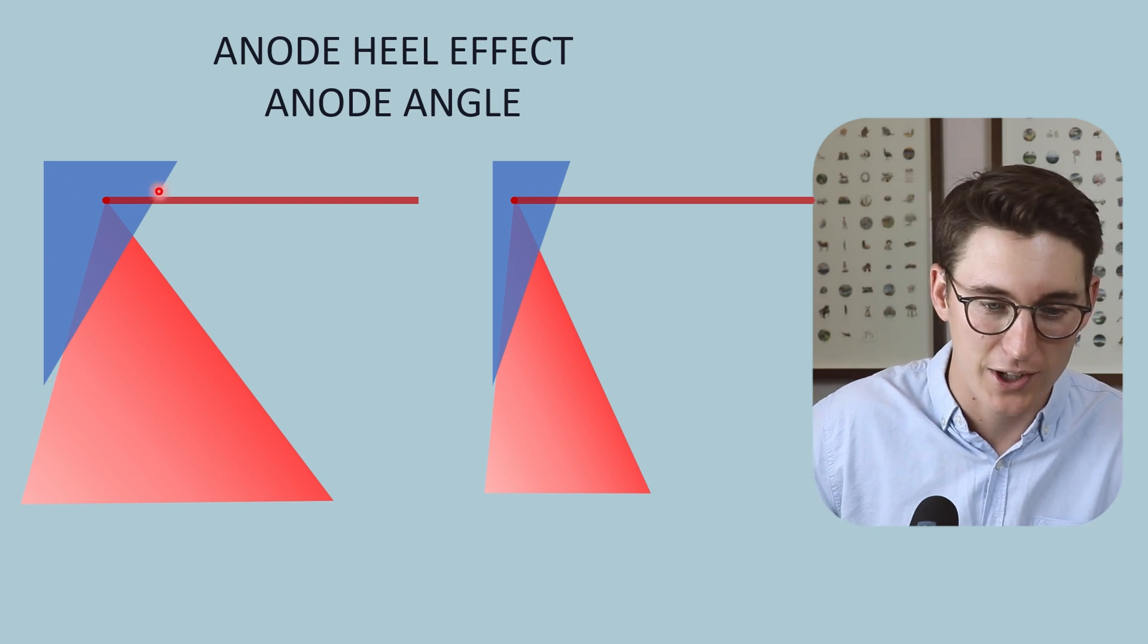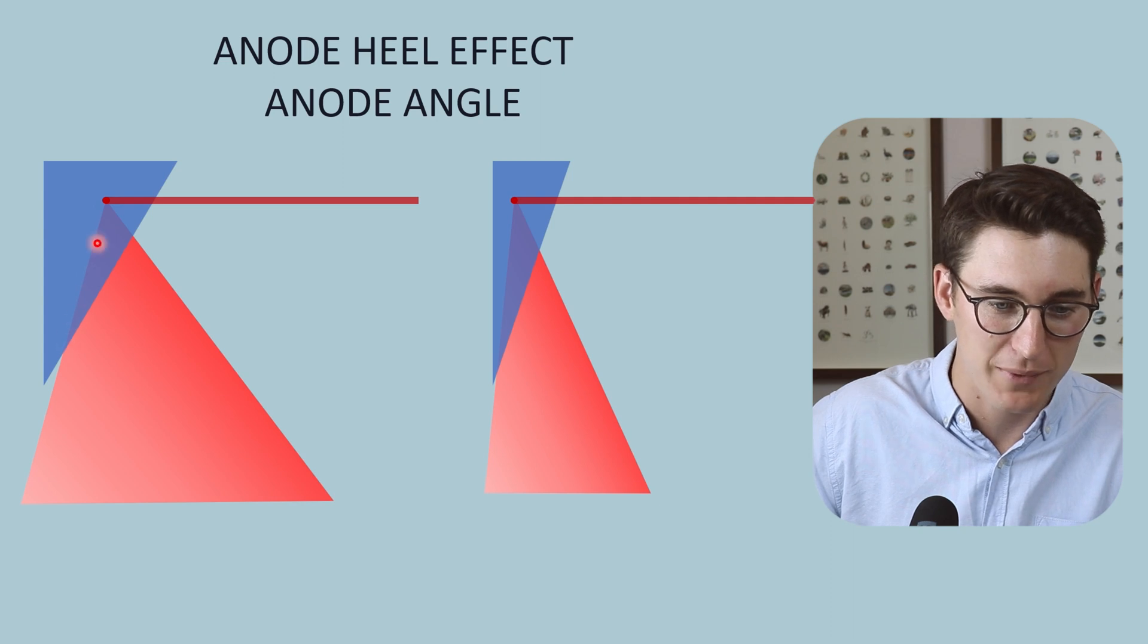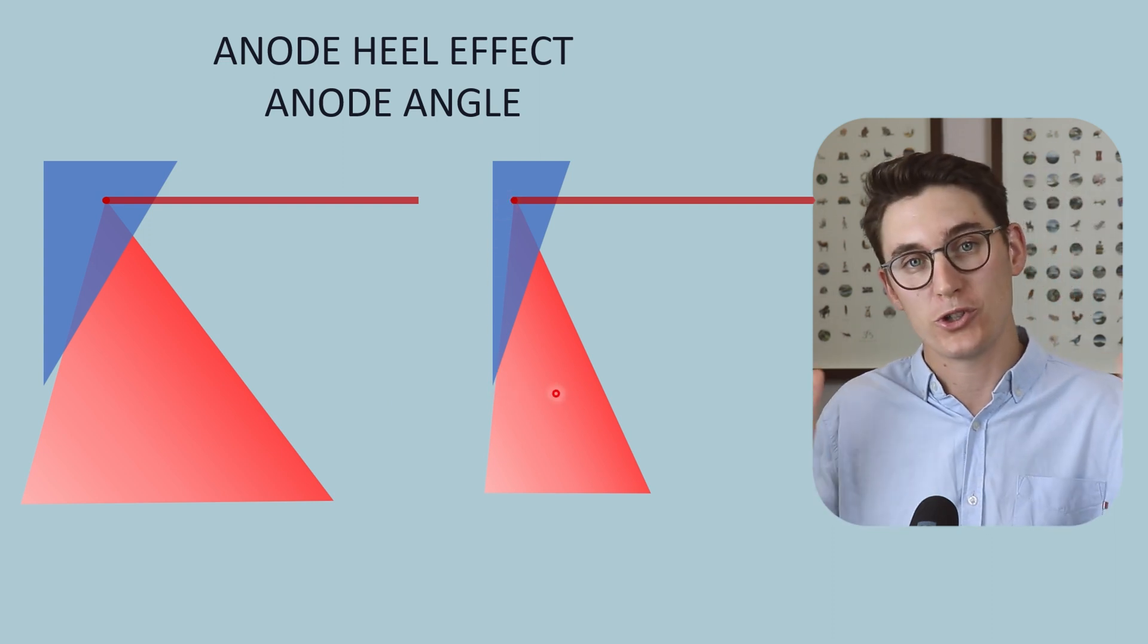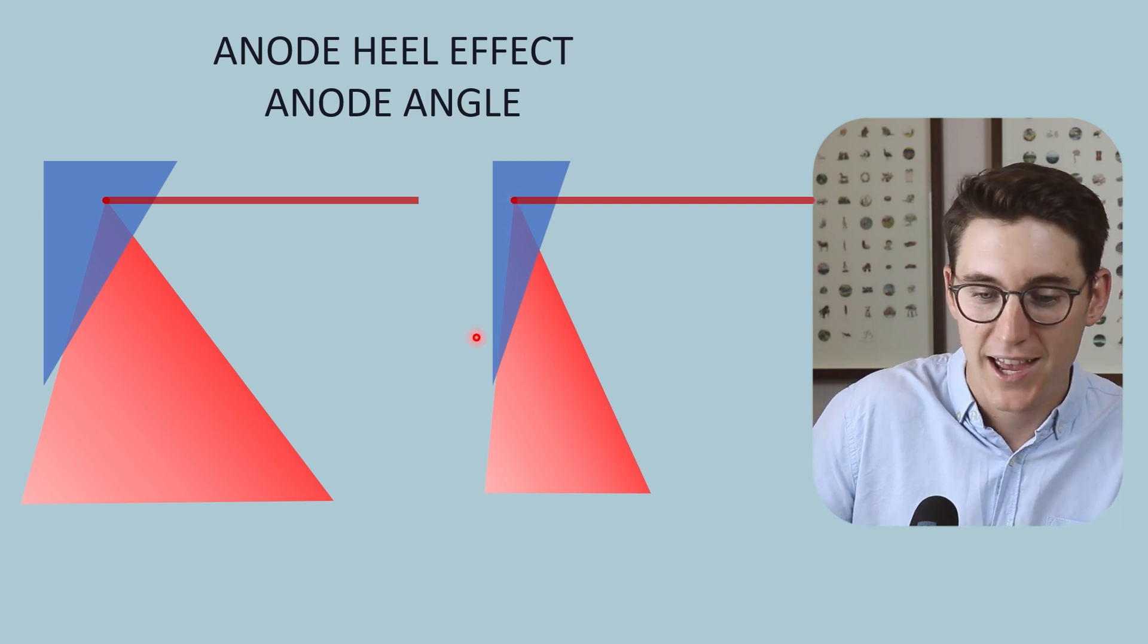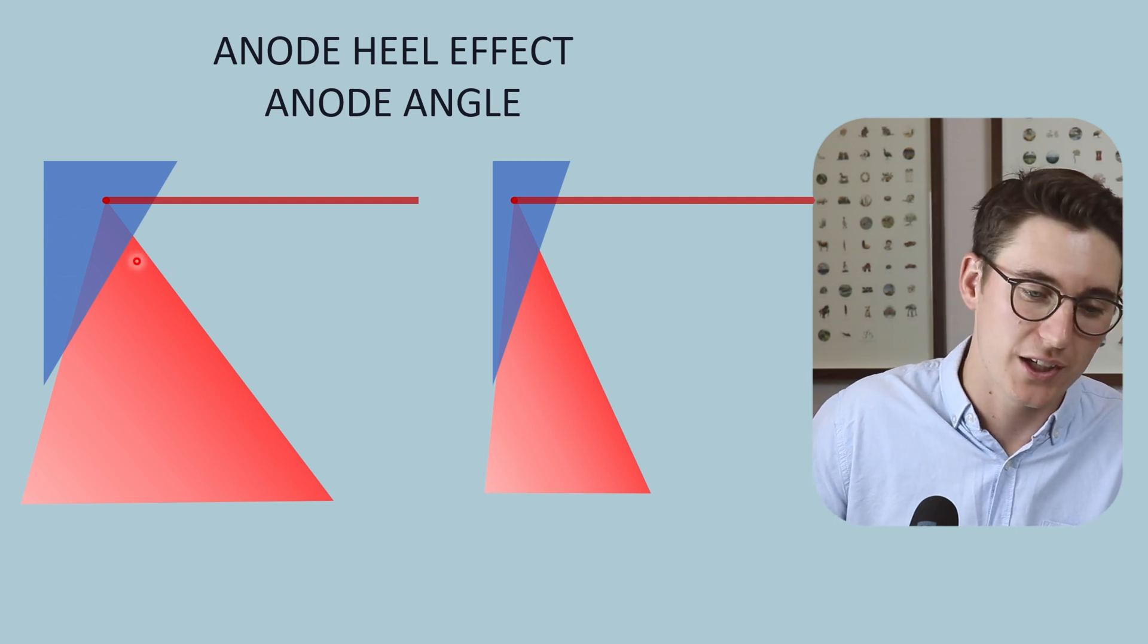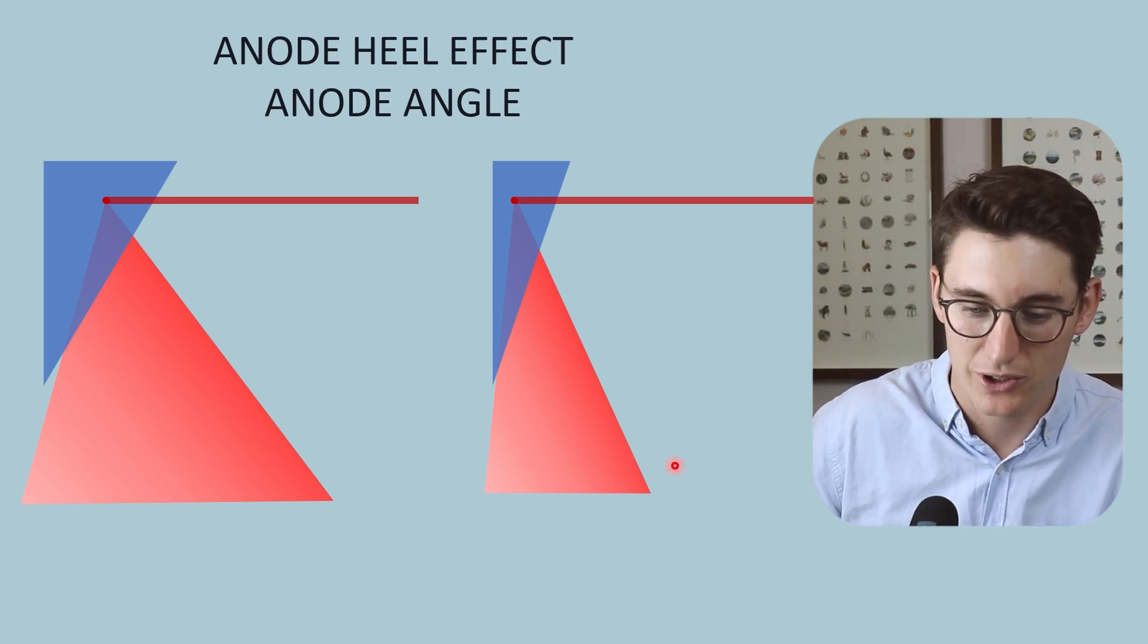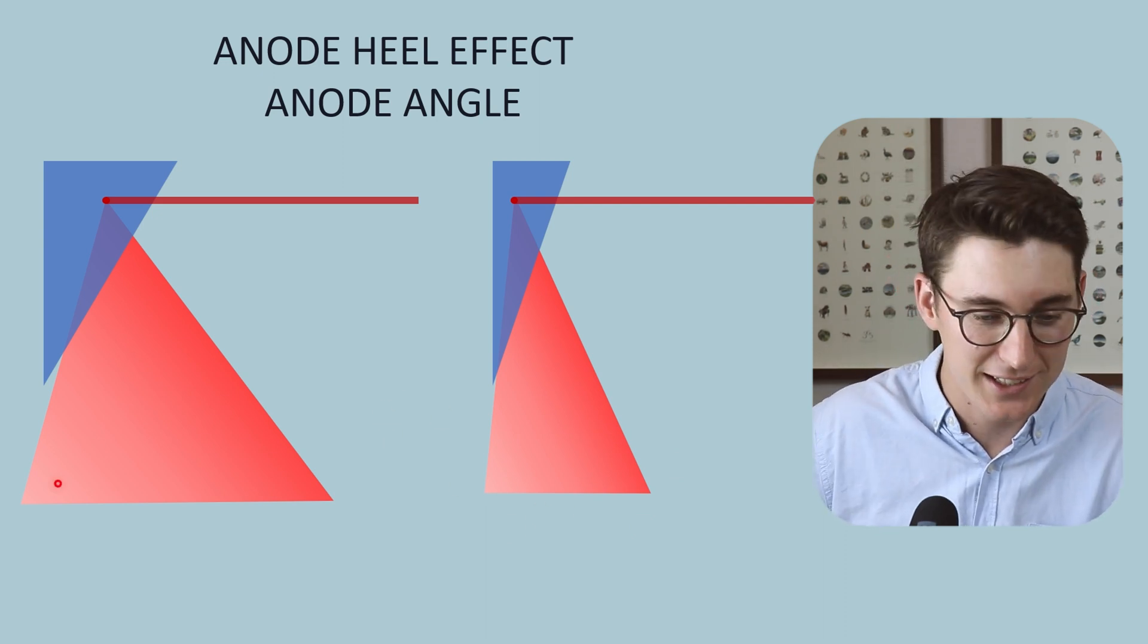You can see that with a larger anode angle, the distance that the anode side of our beam has to travel through the heel of the anode field is less than for a smaller anode angle. When we reduce our anode angle, the heel or the effective heel gets bigger here and our anode side of our field has less intensity than it would in a larger anode angle. Reducing that anode angle increases the heel and increases our anode heel effect. So if you want to reduce the anode heel effect in our x-ray field, we can increase our anode angle.